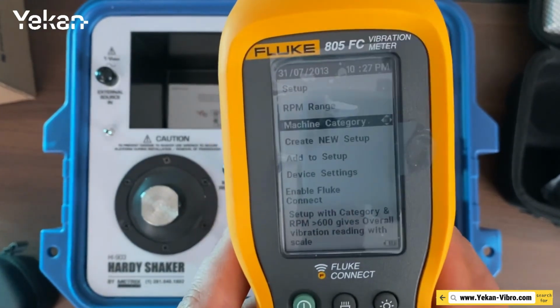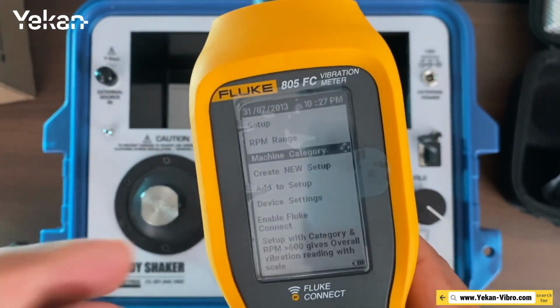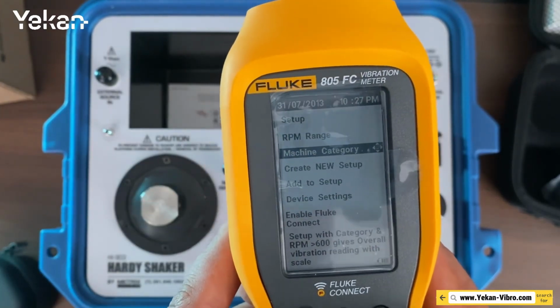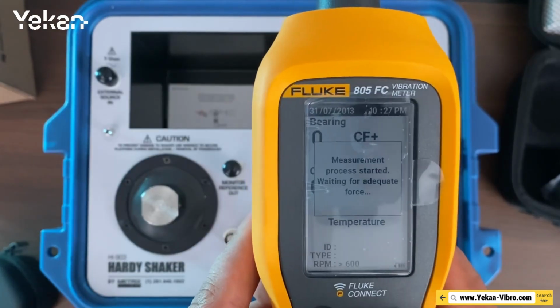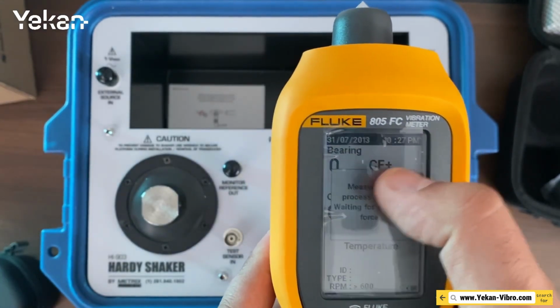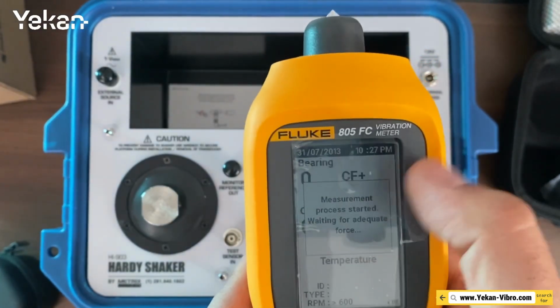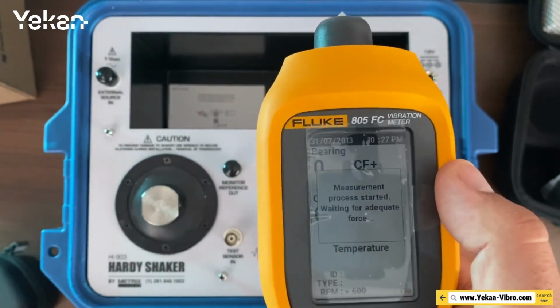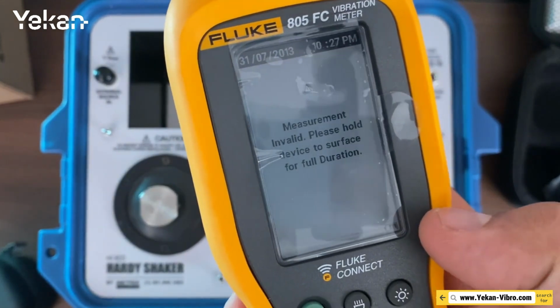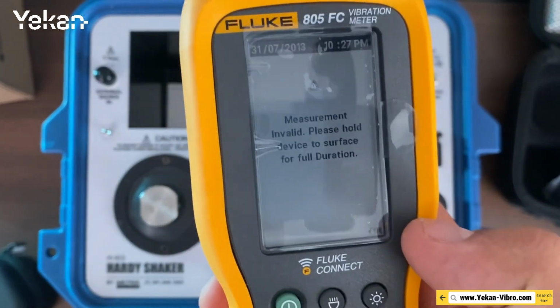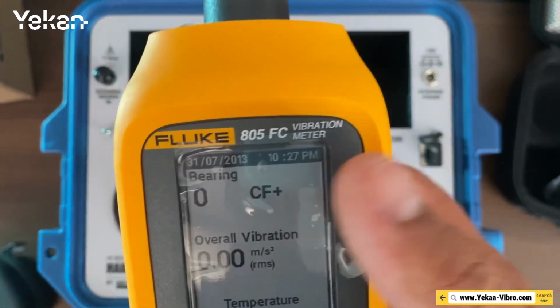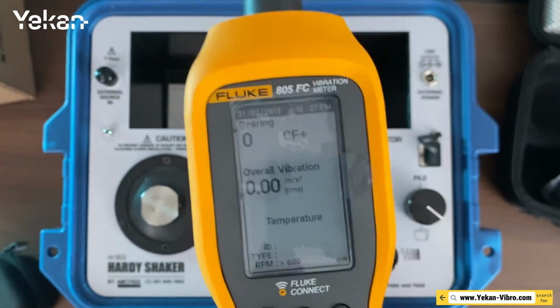What is machine category for? Let me bring up the main screen. This is the section that shows bearing information. As I mentioned, it works based on ISO standards. When you wanted to evaluate based on the standard, you need to define your machine, what type it is, how many kilowatts, whether it is horizontal or vertical, and what RPM it operates at.